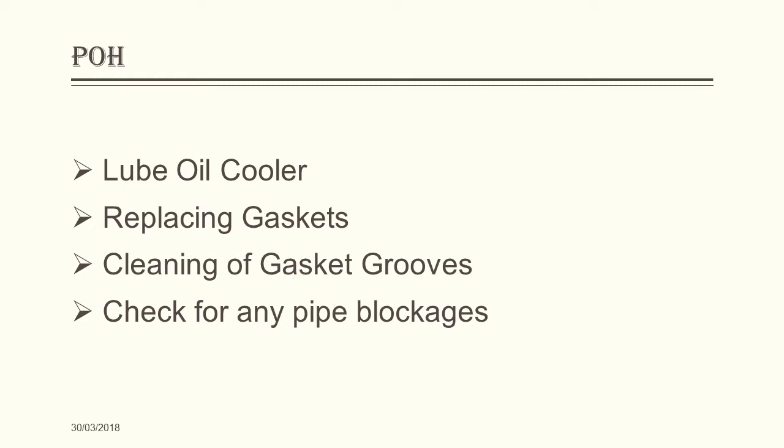For cleaning of gasket grooves, clean the gasket groove by nylon brush with soda ash or a solution of water and synthetic detergent, or use any solvent such as acetone. Also check for any blockages of lube oil piping and water piping in case the lube oil is getting heated up instead of getting cooled.